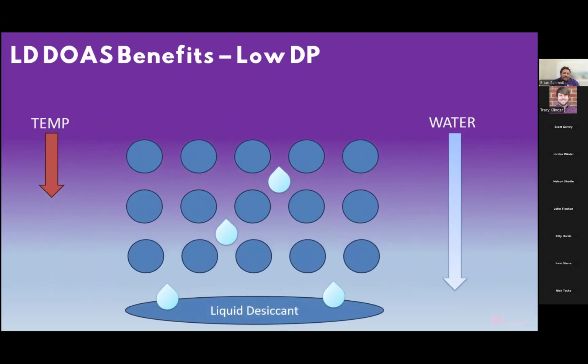So instead, if we were to put in something like a liquid desiccant that absorbs water without necessarily having to manipulate temperature, we can absorb more moisture at a higher temperature. And I'll show you that psychrometrically here in a little bit. But again, this is allowing for essentially absorbing the moisture out of the air separate from just temperature control.